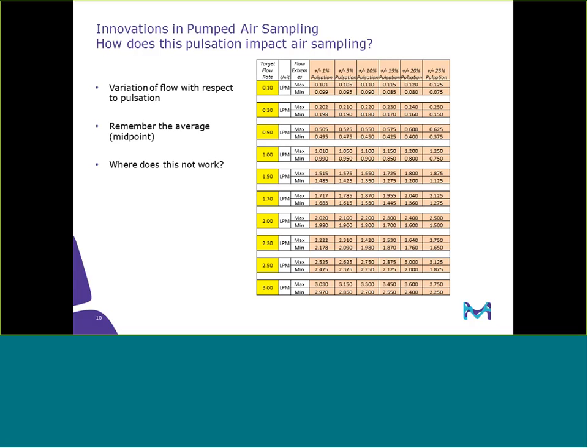And as you can see, for example, if you look at the target flow rate of 1 liter per minute in the left-hand column in yellow, and look across to the maximum plus or minus 25% pulsation, what you set the flow rate to at 1 liter per minute could be anywhere from 1.25 liters down to 750 mils. So you can see there's quite a bit of swing.